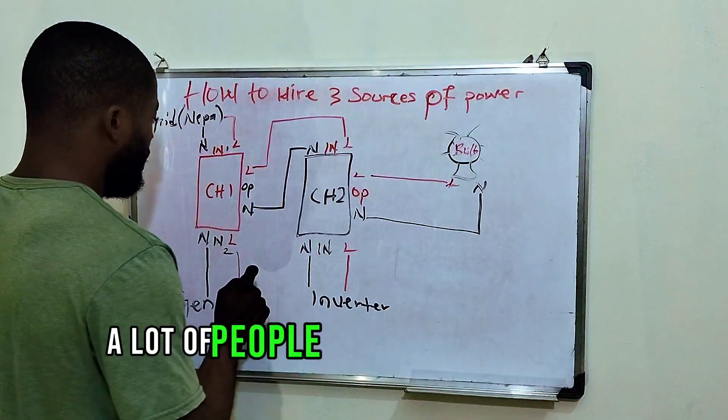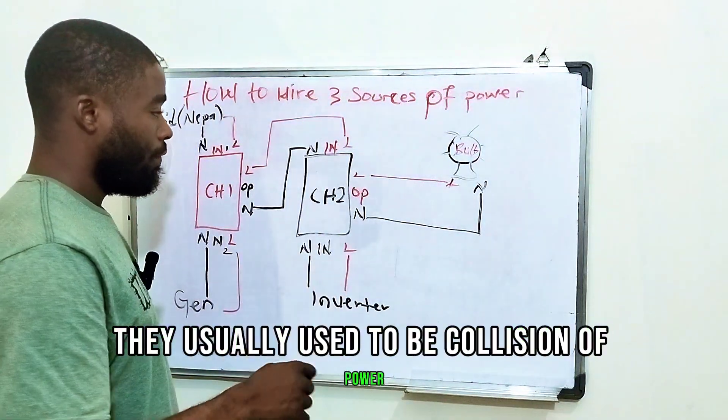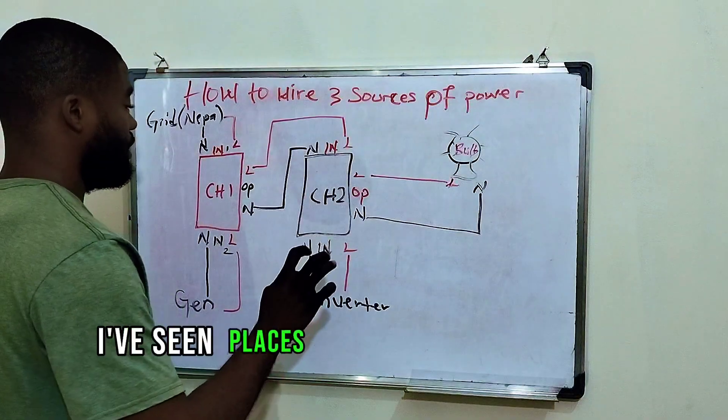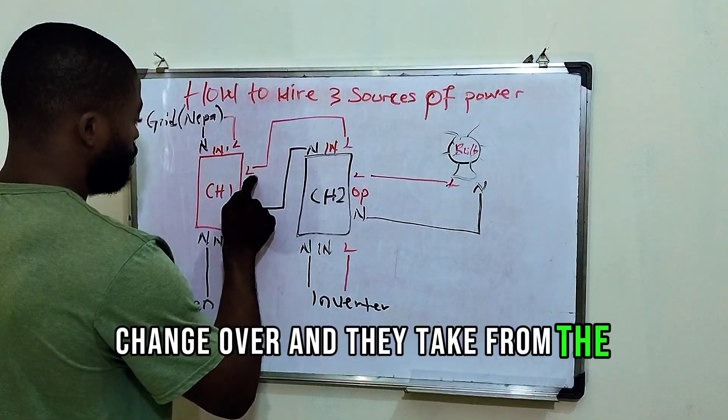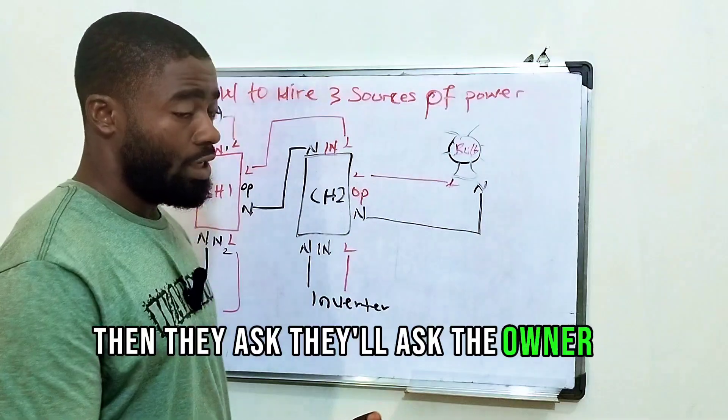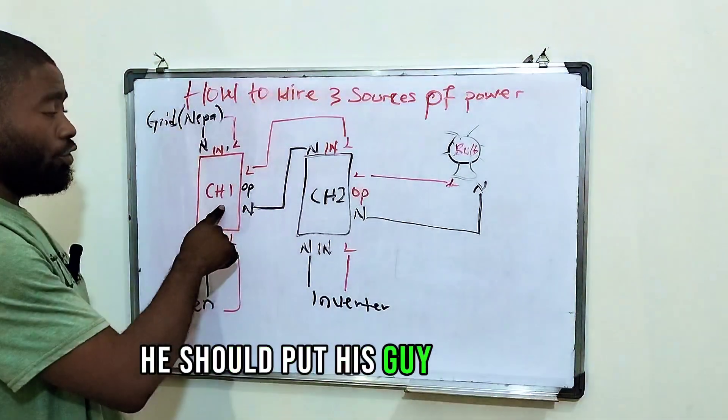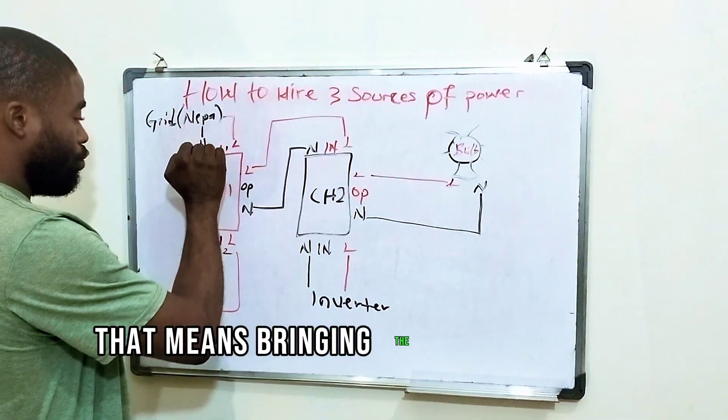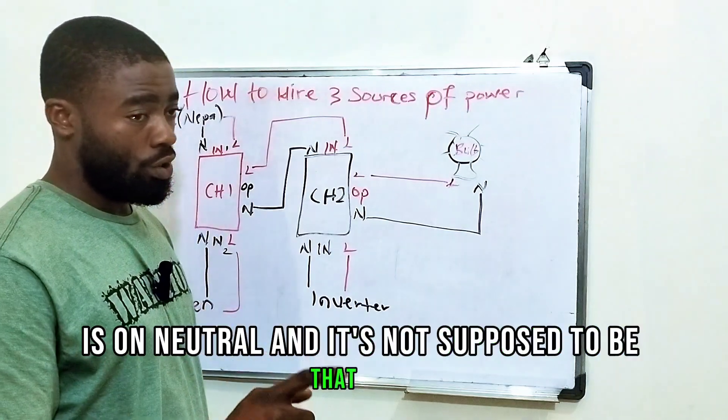The way a lot of people connect them, there usually ends up being collision of power. For example, I've seen places where some people wire these two manual changeovers and they take from the output of this one to the output of this one. Then they'll ask the owner of the house that whenever he wants to use inverter, he should put this one on neutral. That means bringing the switch to the middle is on neutral and it's not supposed to be that way.